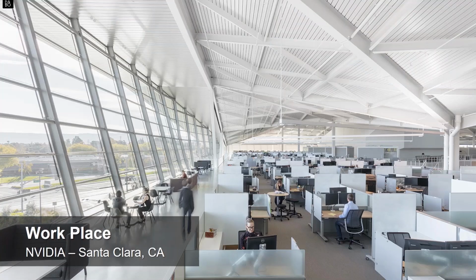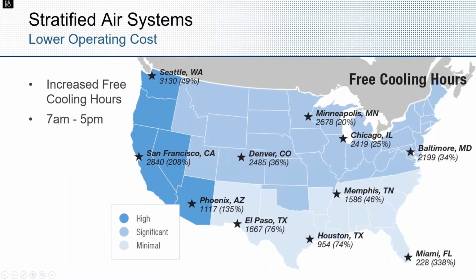Excellent question, thanks for asking that. So that percentage is the increase by going to displacement ventilation over a 55 degree Fahrenheit air delivery system. Roughly that 3130 is the number of hours of displacement free cooling, and that's a 50% increase over what you would have with a traditional system.